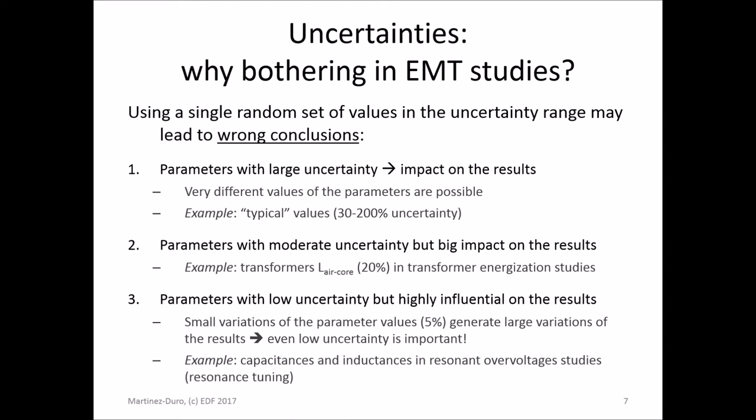The third case is that even when parameters are very well known with small uncertainty — say 5% — in some cases, very small variations of these parameters lead to very high variations of the results. This is typical of studies dealing with resonances, where very small variations of capacitances or inductances can completely change, for example, the overvoltage.